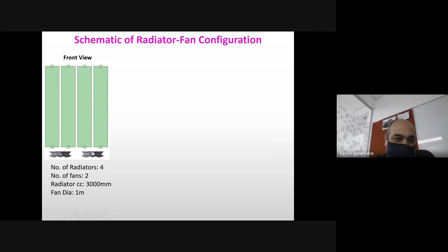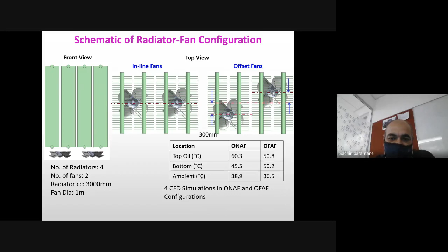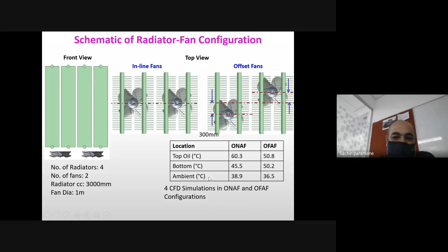The second configuration is where the fans were offset. That means this left fan is placed 300 below the center line, and this right fan is placed 300 above the center line. And these are the boundary conditions which are used for the different cooling configurations. Top oil temperature is 60 and bottom oil is 45. Top is here, bottom is here, and linear temperature is specified on the fins of the radiator, and ambient temperatures are shown over here.